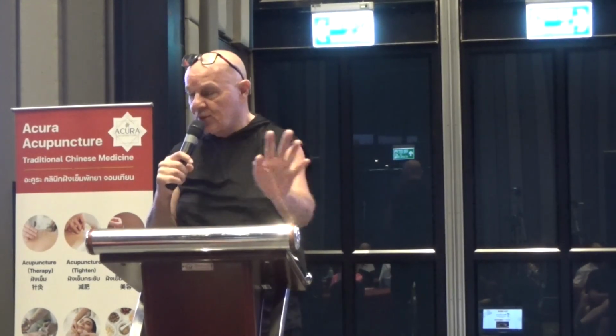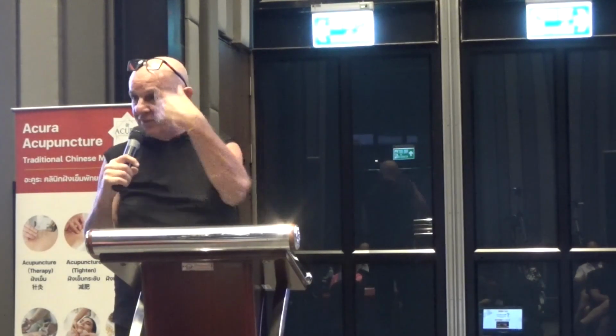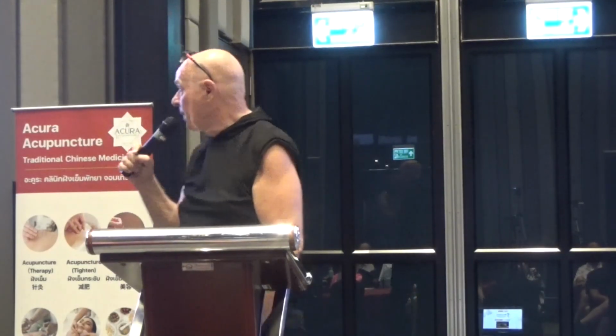There are some simple tests. You may have an earth system, but is it connected properly? Are the wires connected, not broken? You can use plug testers - plug it in and it tells you whether it's wired correctly, whether the earth, neutral and live are in the correct places. Do you have an open system, meaning your neutral, where the amps return at zero - the amps carry your energy, and after it's consumed, the amps go back to the transformer.